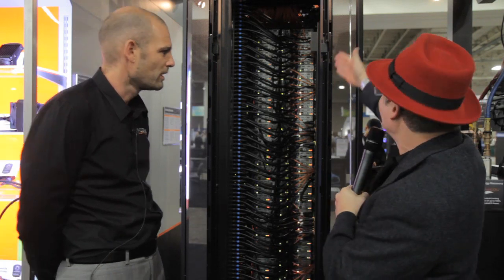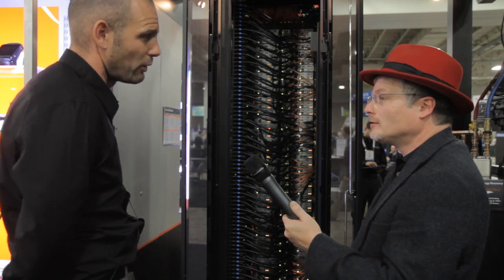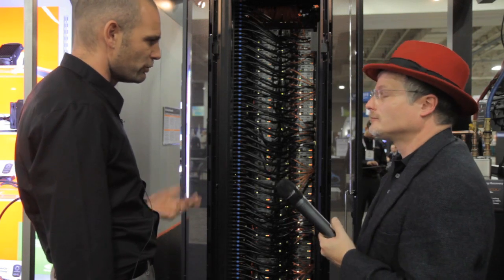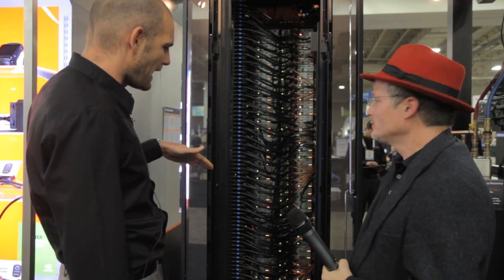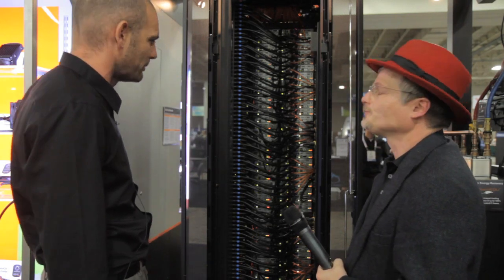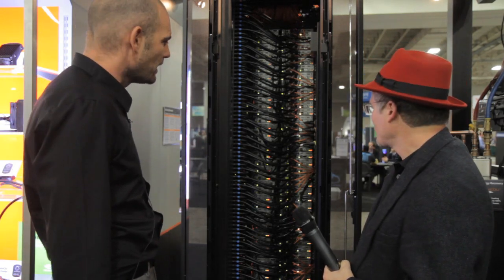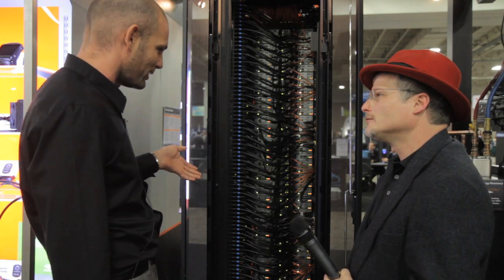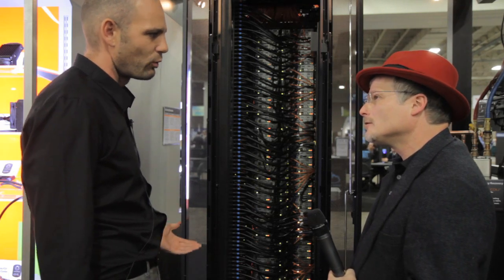What are we looking at here, Andre? We've got a full rack. So this is actually a larger rack than normal — this is a 48U rack. We actually have 92 nodes with 235-watt processors in each. When you add it all up, you have 40 kilowatts of power here. It's probably the most dense and powerful rack you can buy today. And the unusual thing about this rack is that, although we put in 40 kilowatts of power, we spend something like 300 watts cooling it.